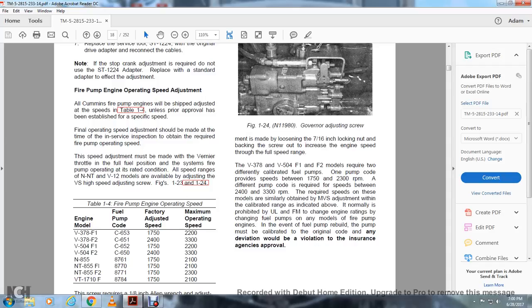The 504 F1 and F2 models require two different calibrated fuel pumps. One pump code is for speeds between 1750 and 2300 RPM. A different pump code is required for speeds between 2400 and 3300 RPM, with the required speed on these models obtained within the MVS adjustable calibrated range indicated above. It is normally prohibited by UL and FM to change the engine rating by changing fuel pumps on any model of fire pump engine. In the event of a fuel pump rebuild, the pump must be calibrated to the original code, and any deviation would be a violation of the insurance agency's approval.